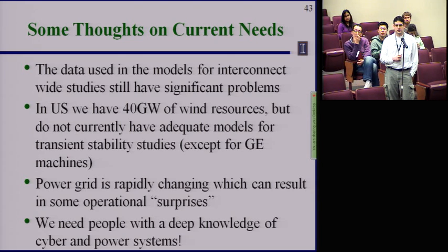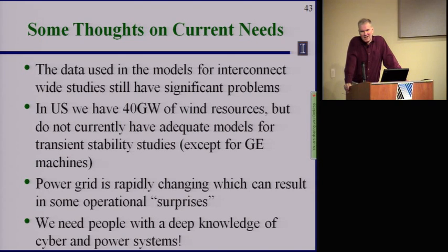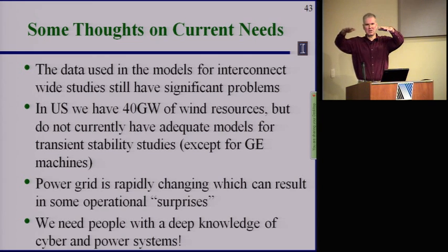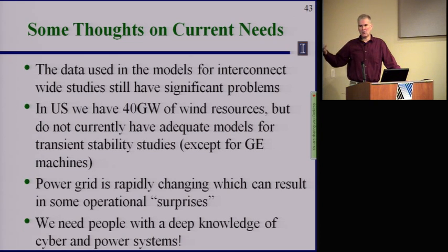What do you mean? To trip a line, all you need is a tree to come in contact or get close enough to the line to trip it. That first line that tripped in the August 2003 event was loaded at about 37% of its rating, so it was not overloaded. Usually when a line overloads, the conductor heats up and sags down. If there's a tree underneath and it gets close enough to arc, it causes what we call a ground fault, and the current flowing will cause the circuit breakers to trip. You can get very high fault current, but the circuit breakers can easily interrupt that.